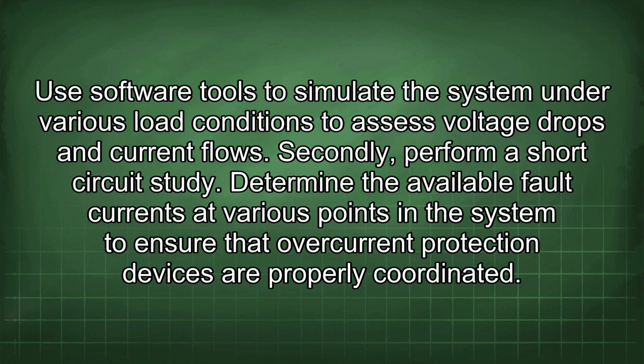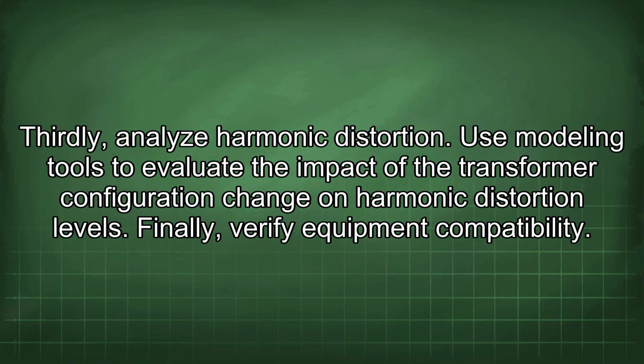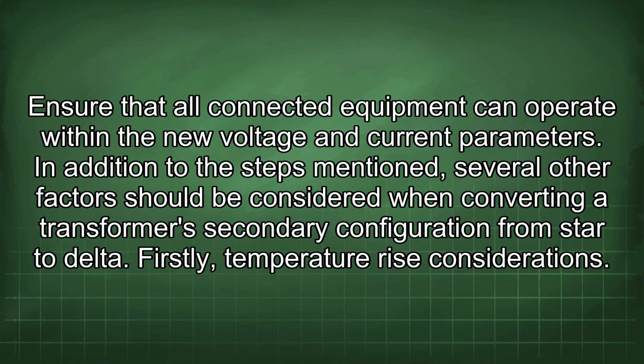Determine the available fault currents at various points in the system to ensure that overcurrent protection devices are properly coordinated. Thirdly, analyze harmonic distortion. Use modeling tools to evaluate the impact of the transformer configuration change on harmonic distortion levels. Finally, verify equipment compatibility. Ensure that all connected equipment can operate within the new voltage and current parameters.